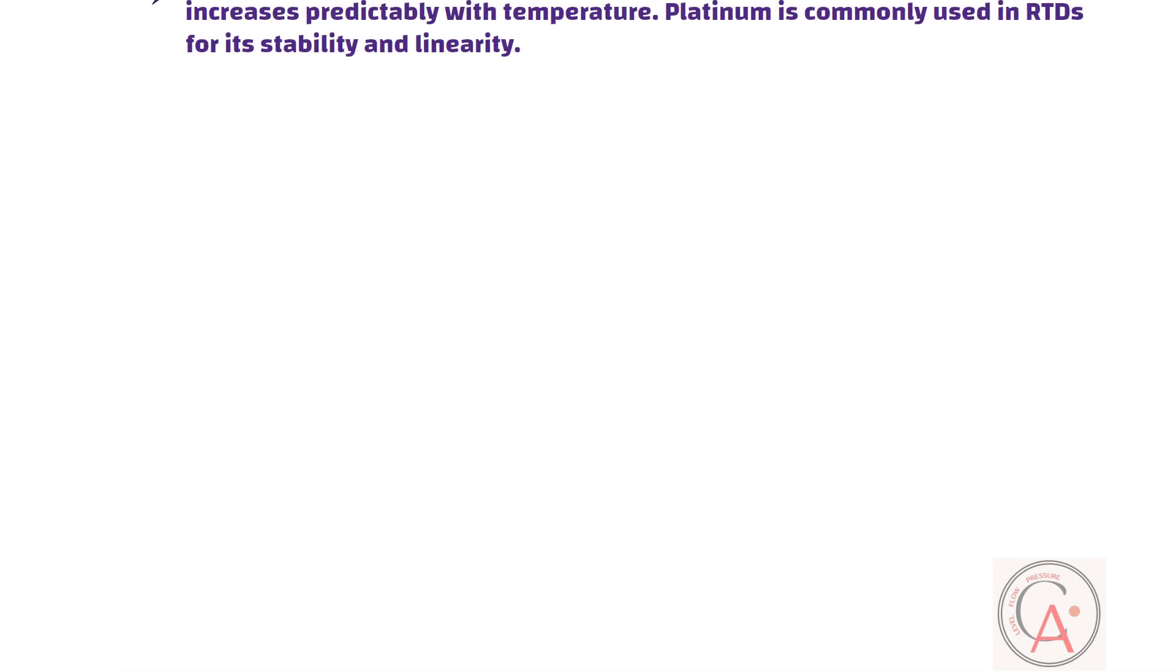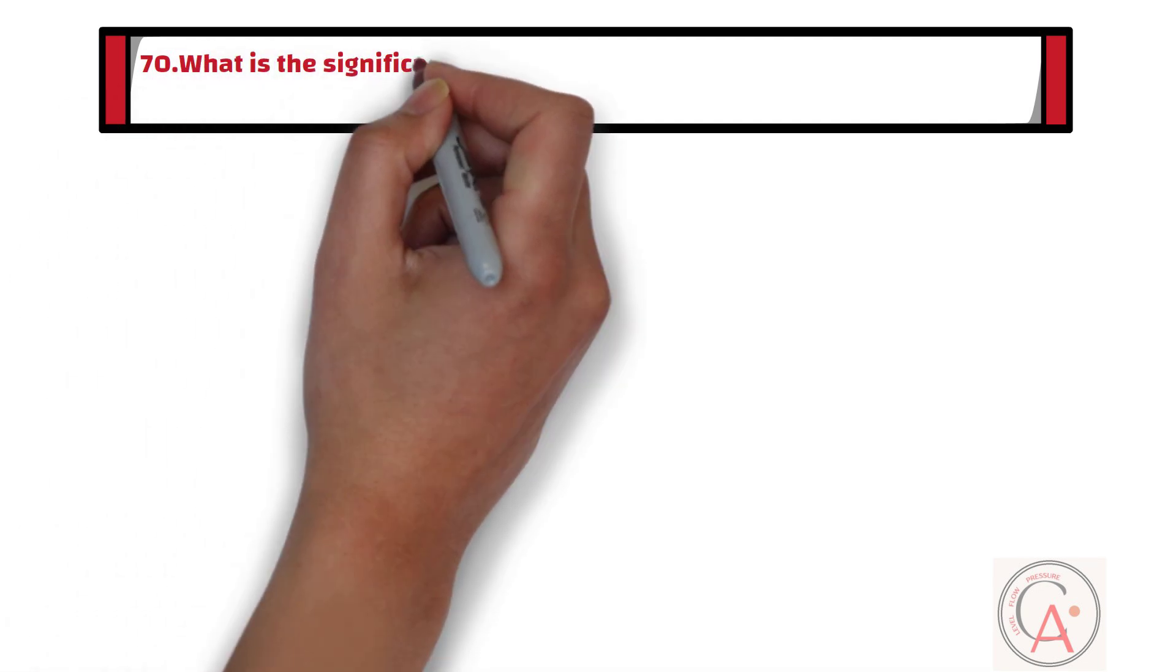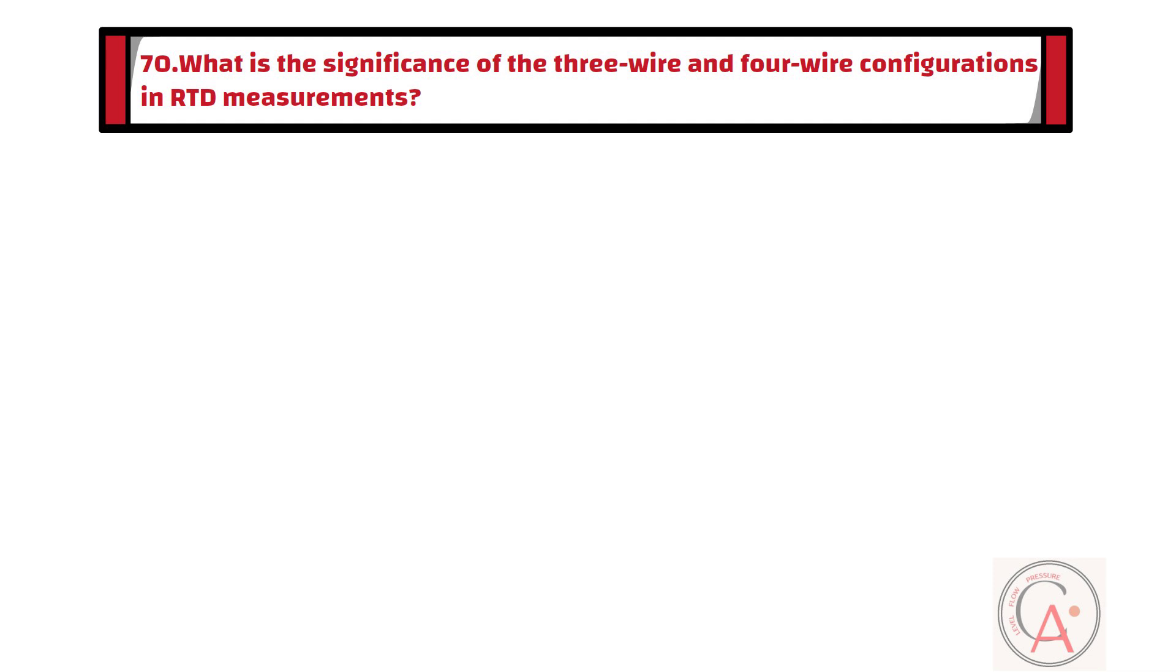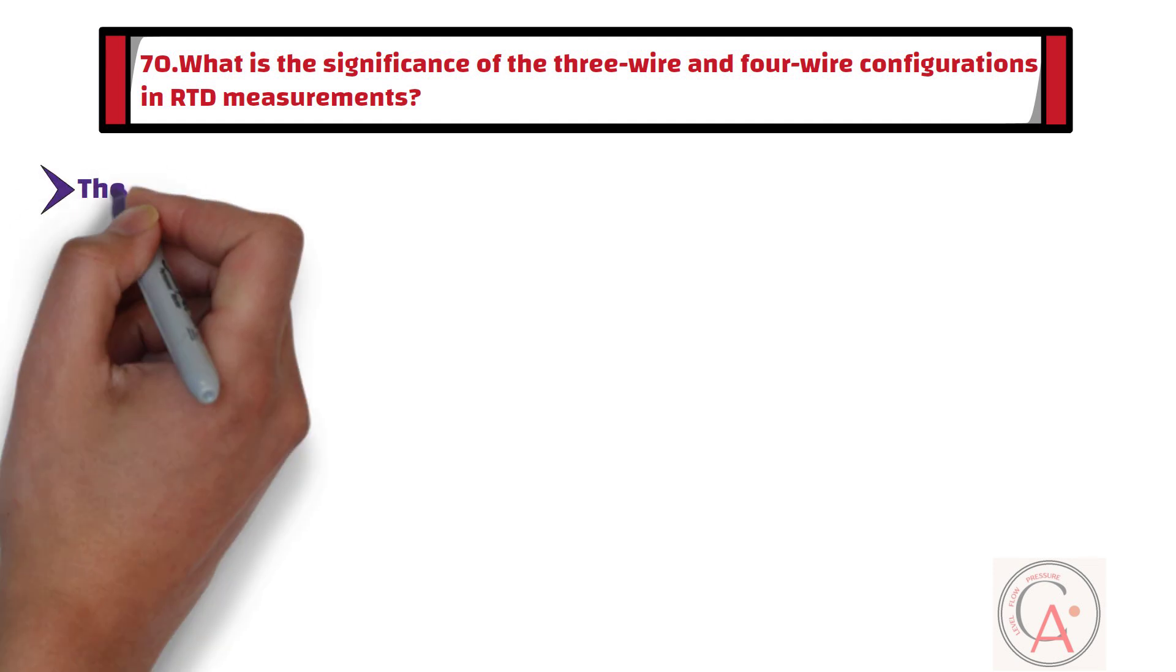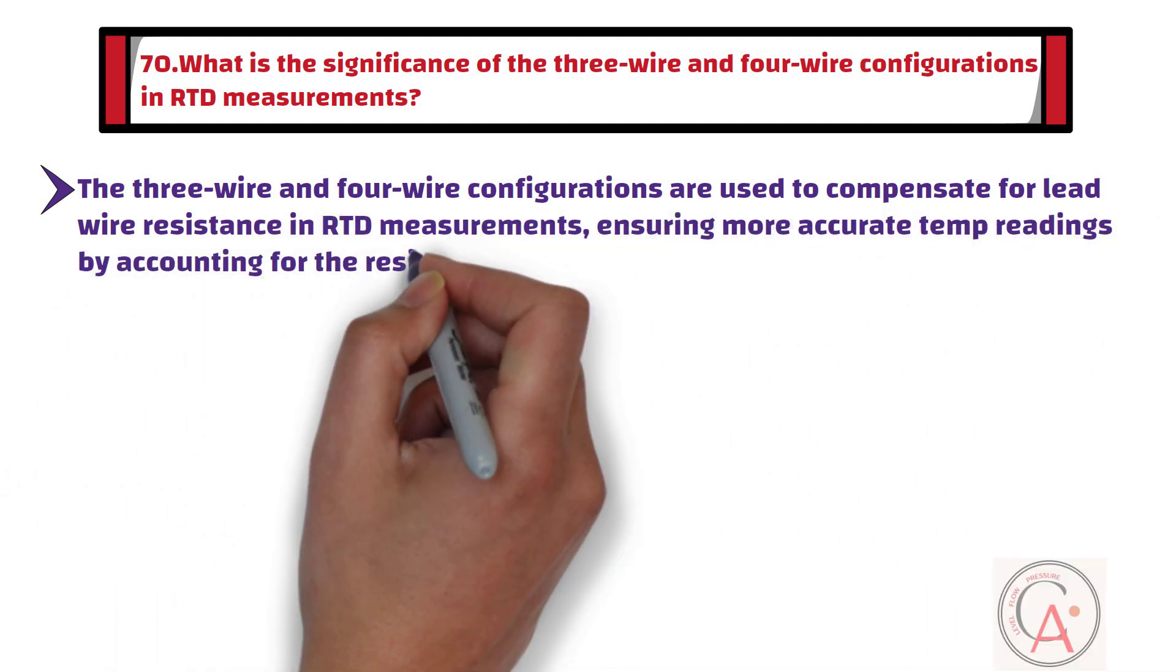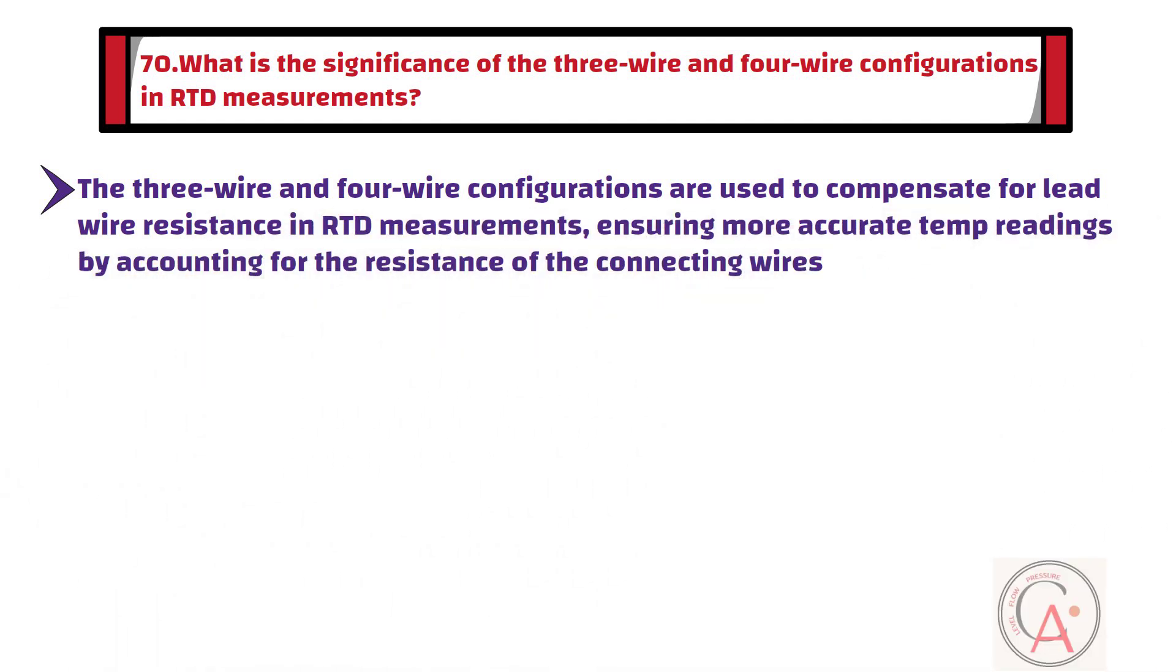Question number 70: What is the significance of the three-wire and four-wire configurations in RTD measurements? The three-wire and four-wire configurations are used to compensate for lead wire resistance in RTD measurements, ensuring more accurate temperature readings by accounting for the resistance of the connecting wires.